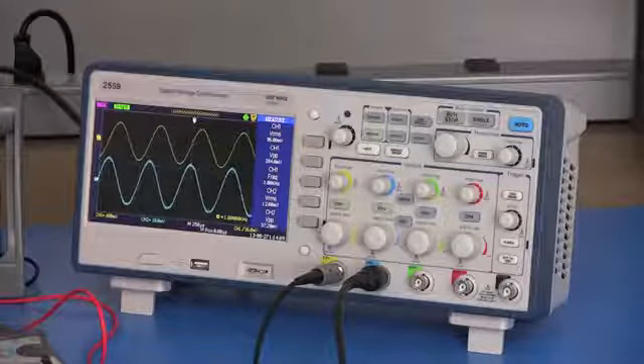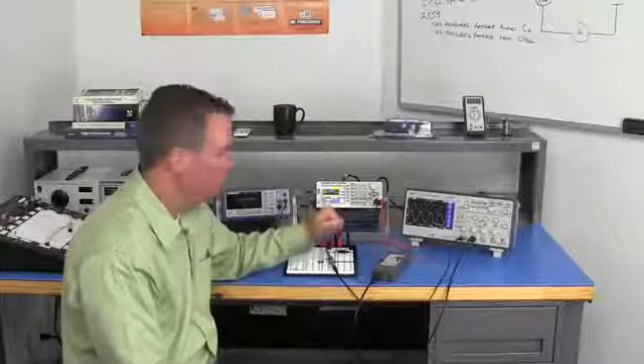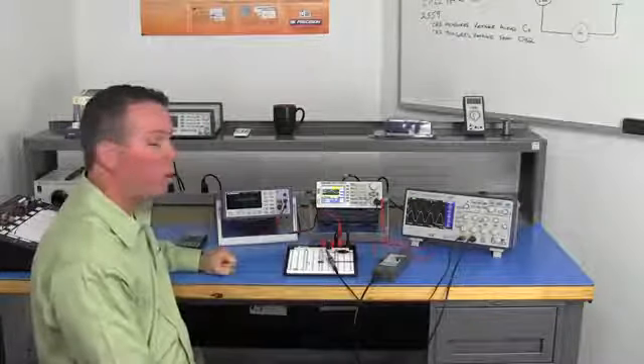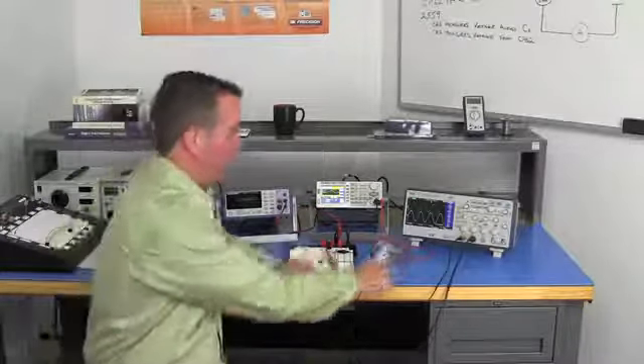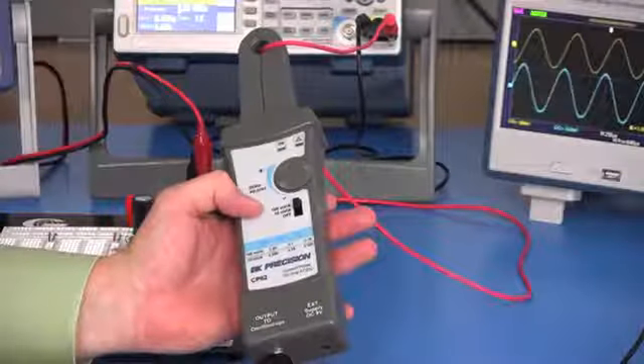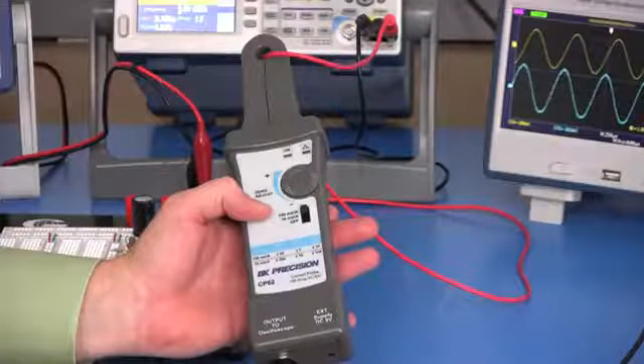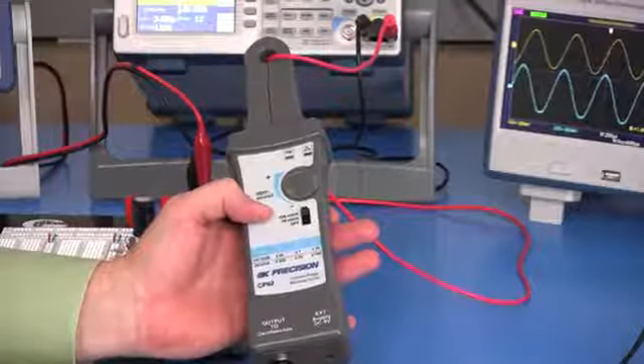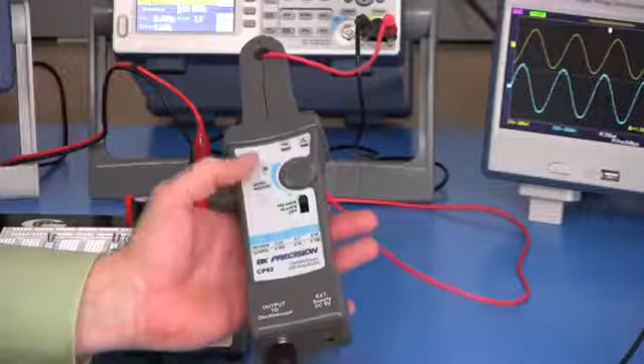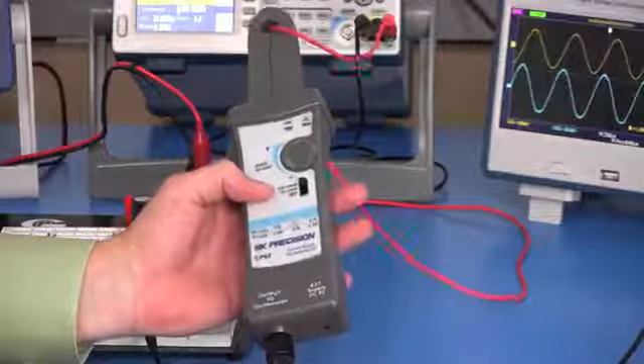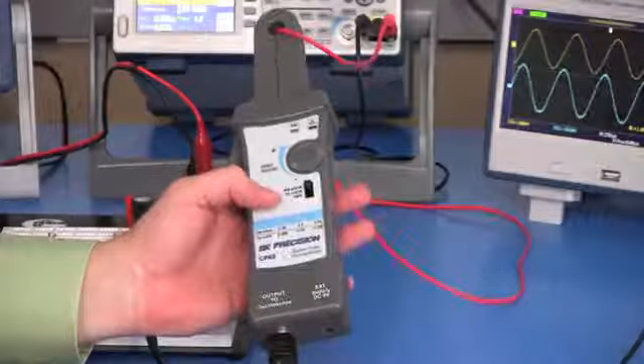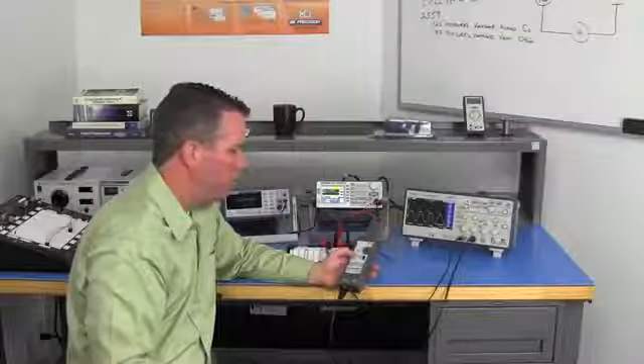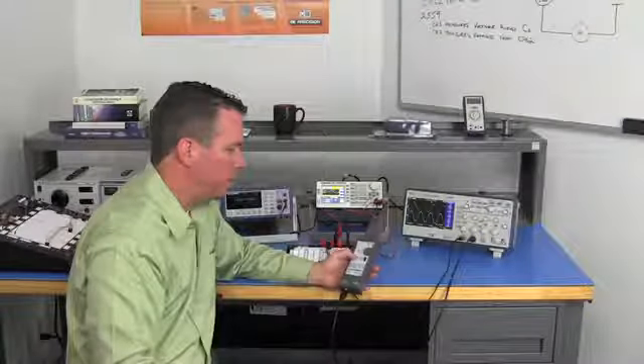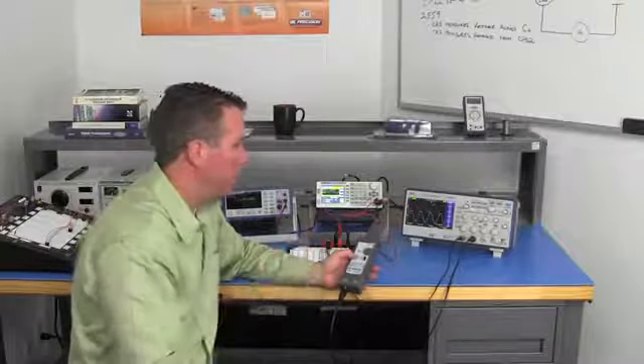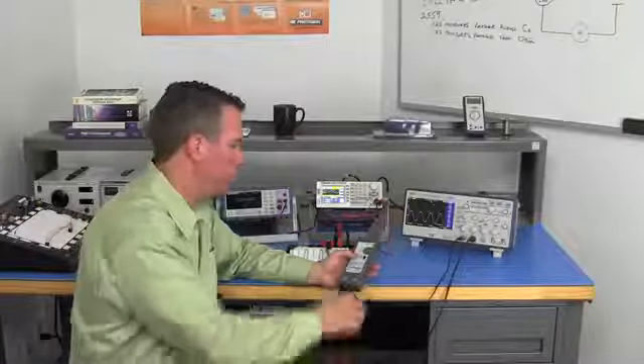It is measuring 12 millivolts, and you can see here I've got 126 milliamps. The way the CP62 works is you've got a 100 millivolt per amp or a 10 millivolt per amp setting. The 10 millivolt per amp is for measuring larger currents, and the 100 millivolt per amp is for measuring smaller currents like we've got here. So if I've got 12 millivolts being measured, and it's set to 100 millivolts per amp, that tells me I'm measuring 120 milliamps.